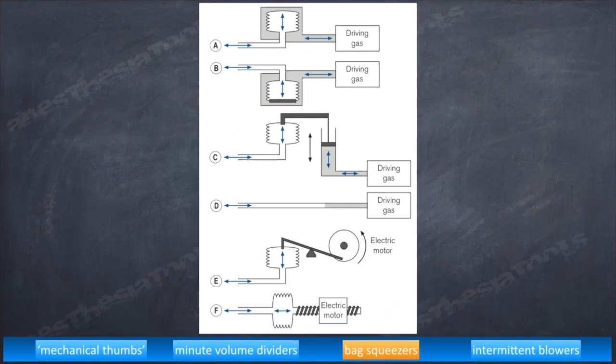These are the various types of bag squeezer ventilators. First one is rising bellows arrangement. B is descending bellows arrangement. C is pneumatic piston with mechanical linkage. D is pneumatic piston. Next is cam-driven linkage from an electric motor. And the last one: screw-threaded piston or worm drive powered by electric motor.